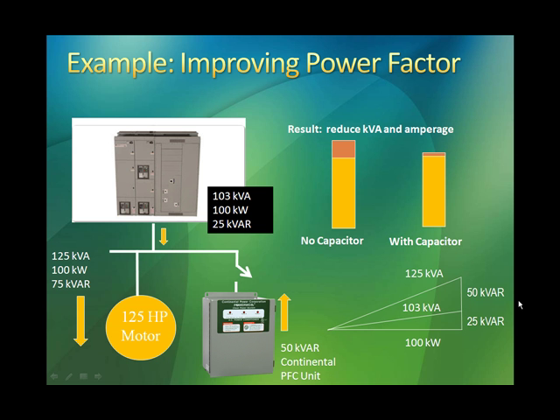If we close the switch there above the PowerWorks, all of a sudden the reactive energy that is needed by the motor begins to flow from the PowerWorks unit. Not 100% of it, but in this case it would be 2/3 of it. So once the switch is thrown, instead of the switchgear and the utility feeding energy through the meter providing 125 kVA, we are now only asking for 103 kVA.